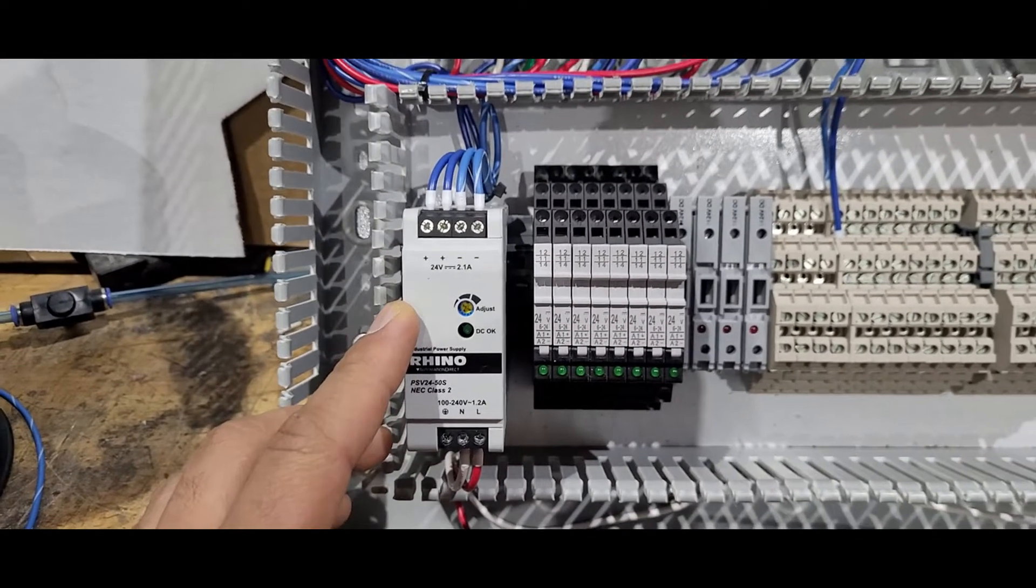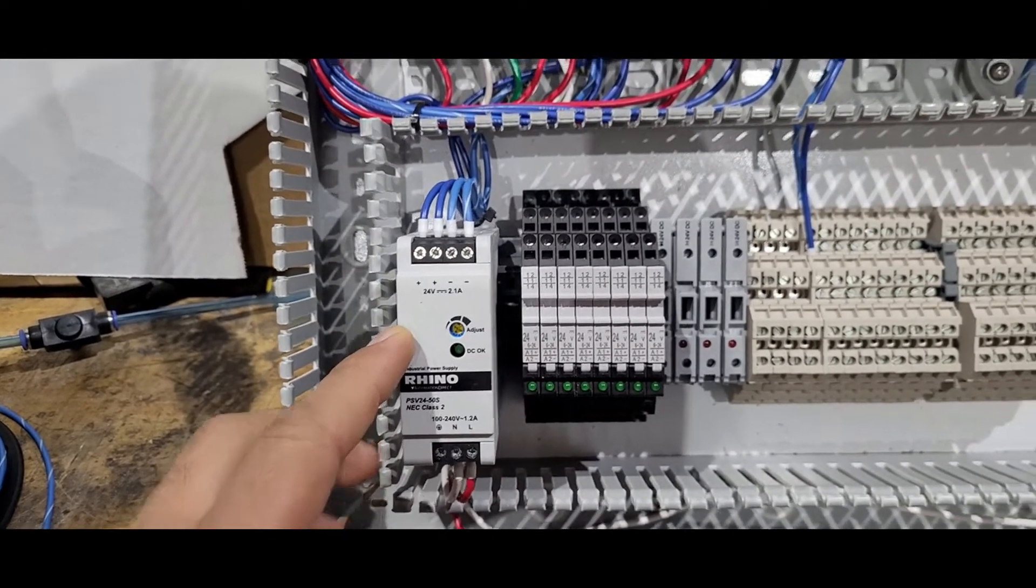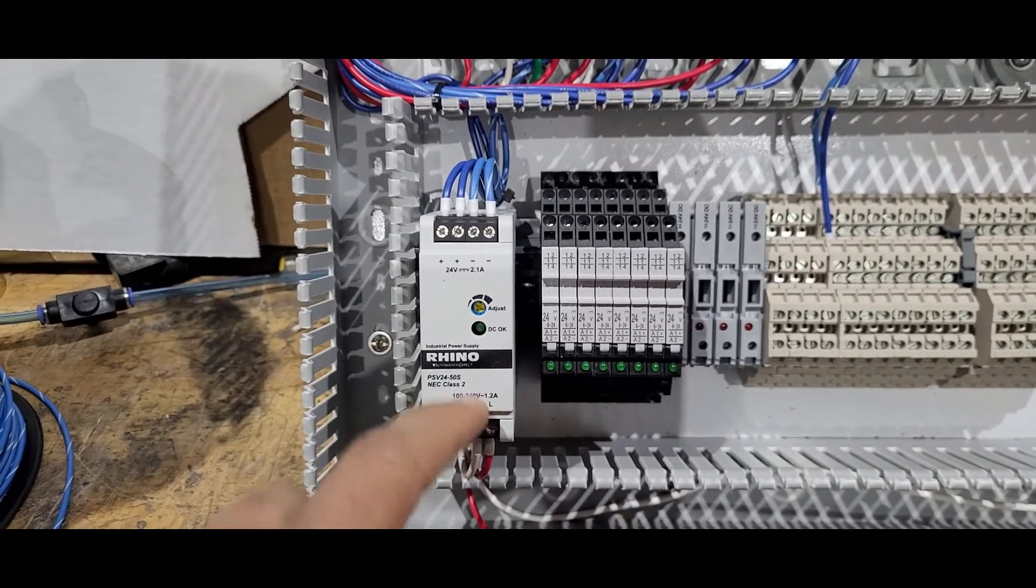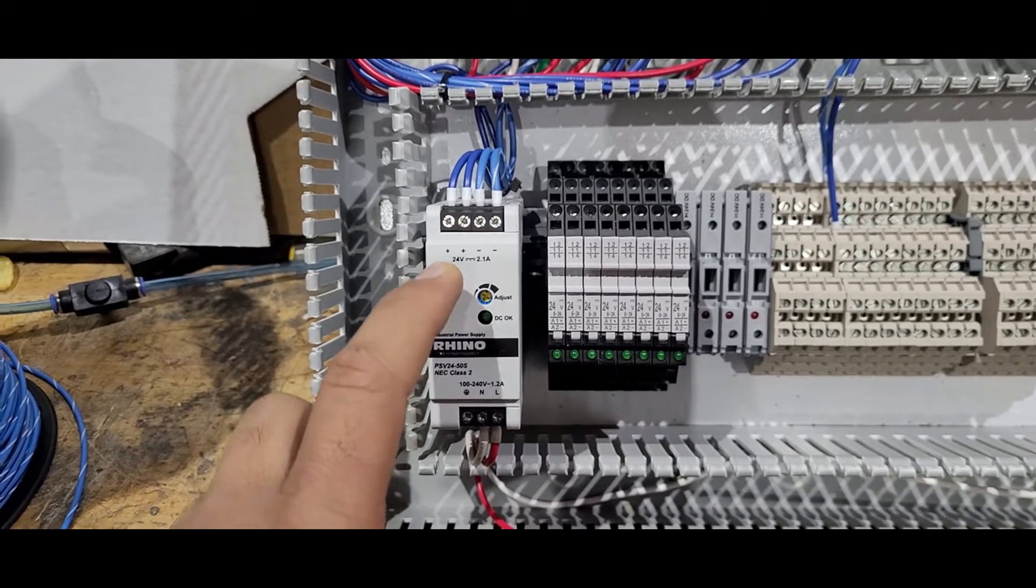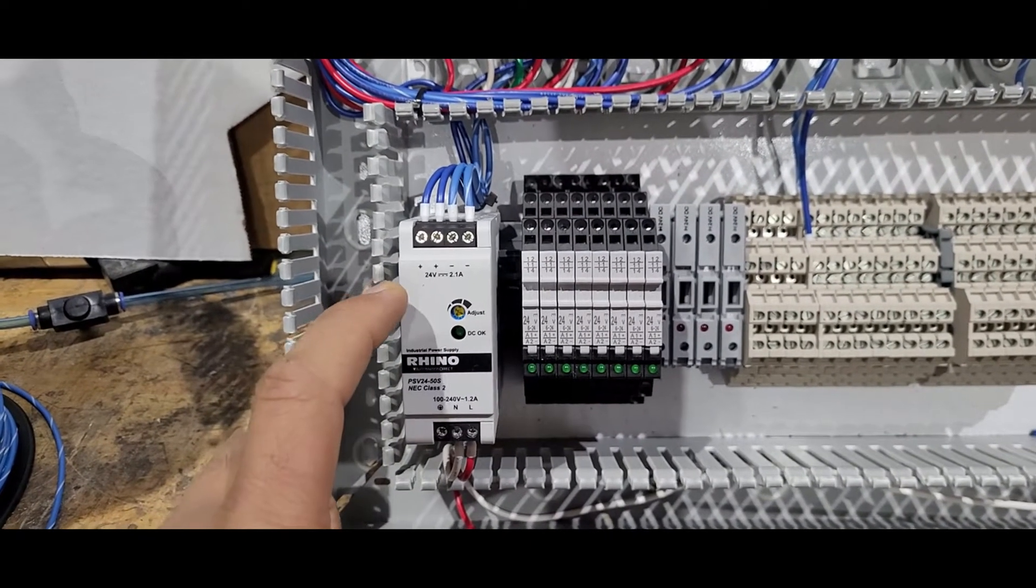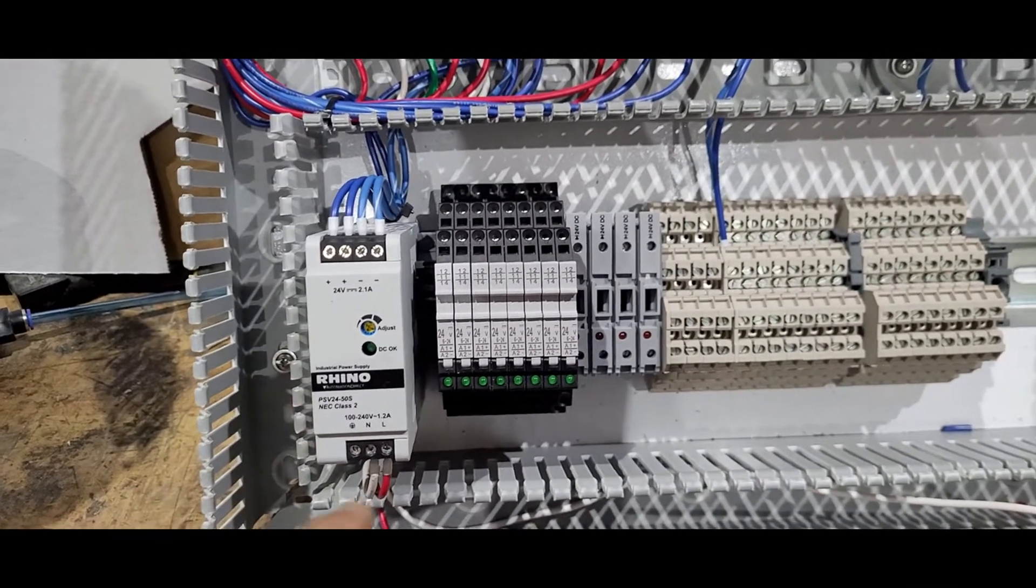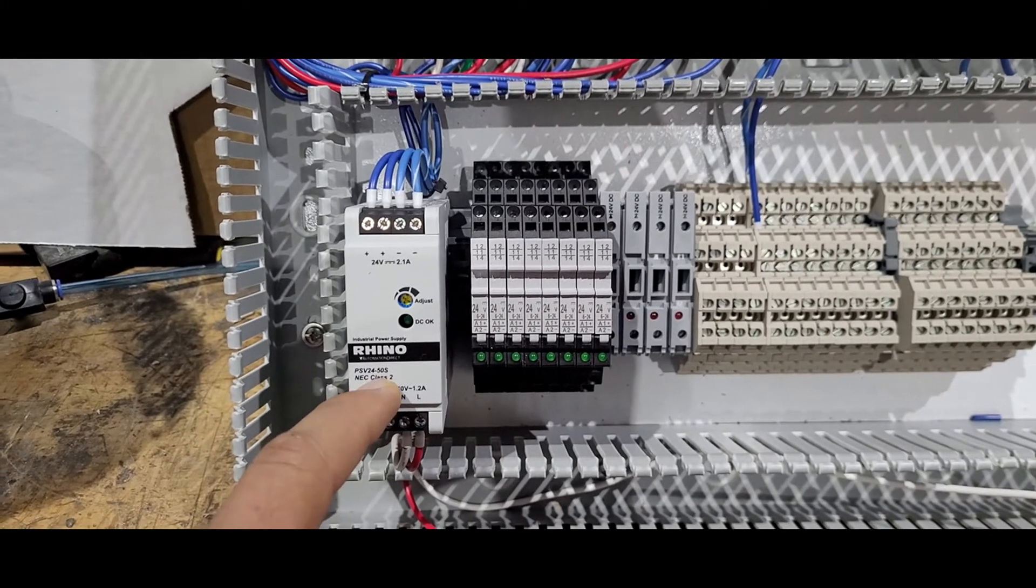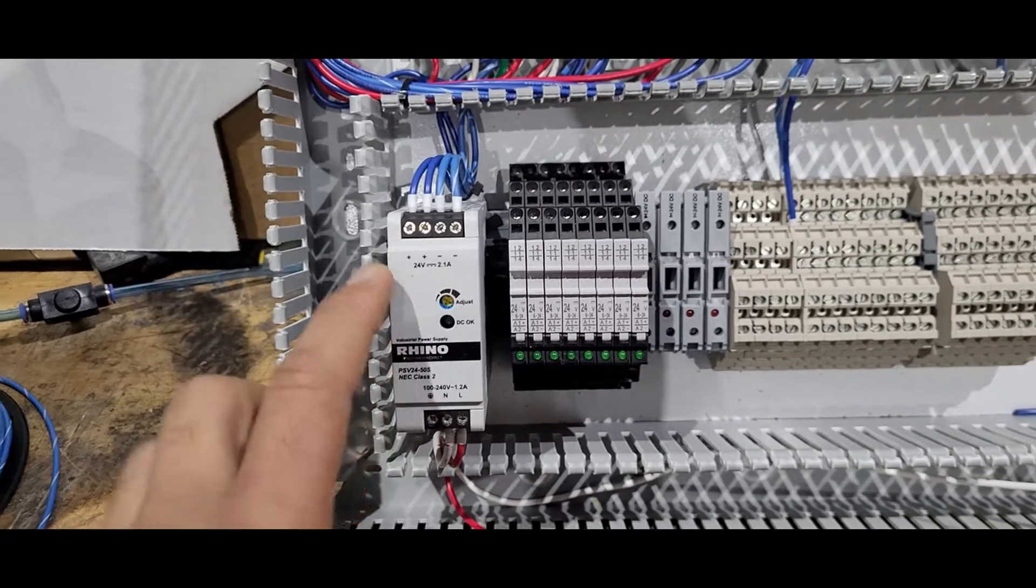Next we have this DC power supply. This DC power supply takes 100 volt or to 240 volt AC and gives us 24 volt DC as output. This DC power supply is important because there are many components that work with 24 volts. I cannot put 110 straight on them; if I do they will burn. So I need some kind of converter. This device will convert my 110 to 24 volt DC.